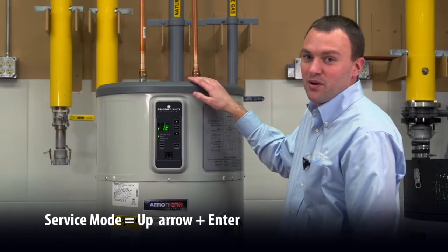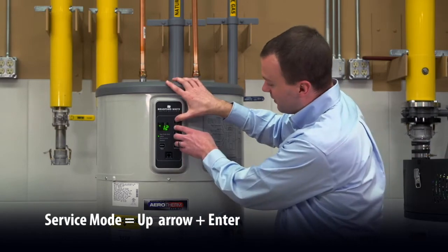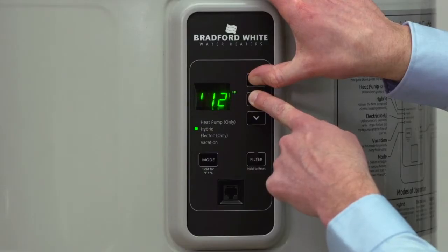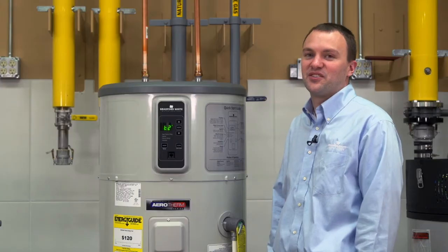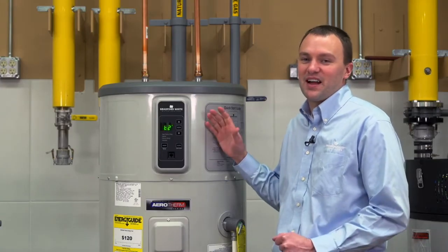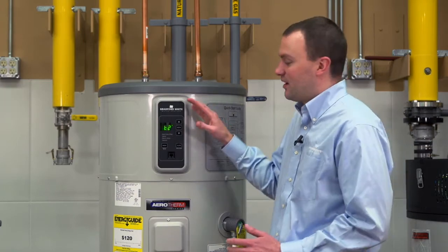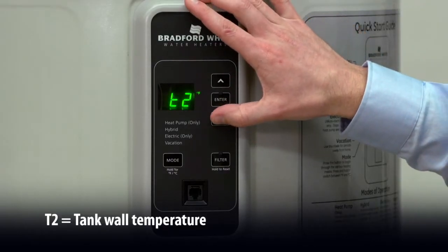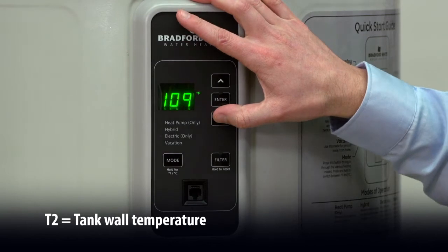To get into service mode, we're going to press the up arrow and the enter arrow. It takes about 5 seconds, and it'll give us a tone to let us know when we're there. So in service mode, we're able to monitor 5 different temperature sensors. Our T2 sensor is our tank temperature. That's going to be 109 degrees.